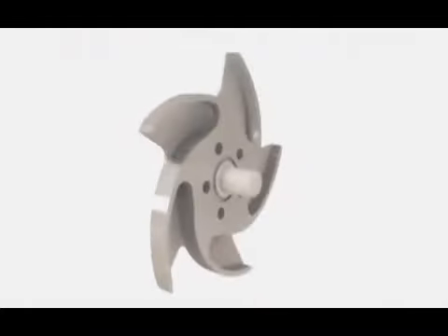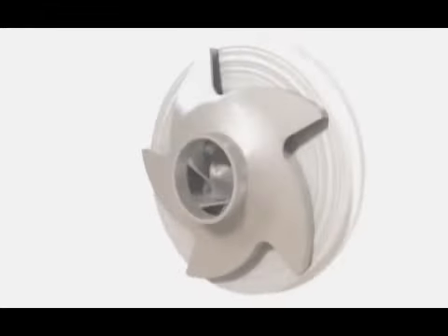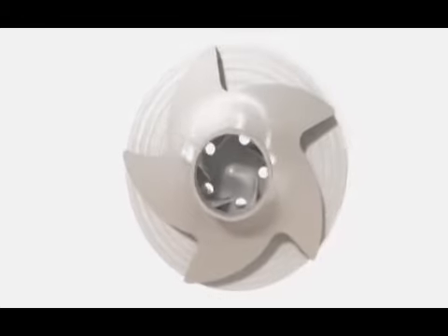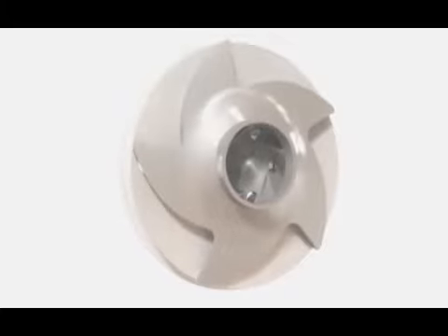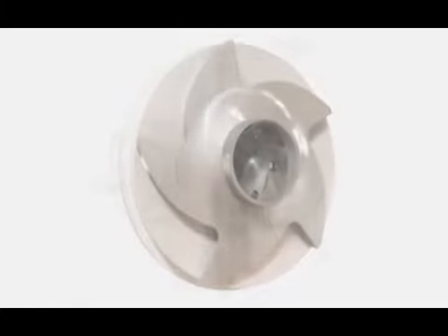With the reverse vane impeller, the rear cover is the active wear surface. The flat rear cover surface can easily be machined or replaced if needed. This simply isn't an option with competing designs where the complex and more expensive casing serves as the wear surface.